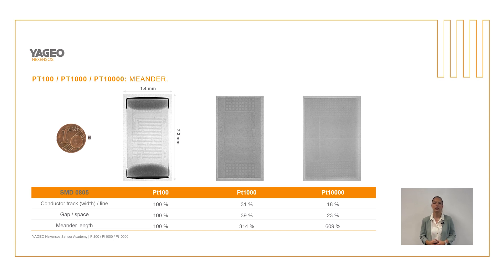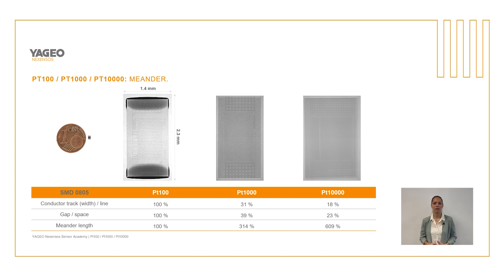From this illustration it becomes clear that with a higher nominal resistance, the width of the conducting path and the width between the conducting paths becomes finer and finer as the meander becomes longer. In the case of the PT10000, the structure of the meander is hardly identifiable even in the highly magnified image. The production of a PT10000 is accordingly complex due to the more intricate meander, and therefore it is not a standard product.